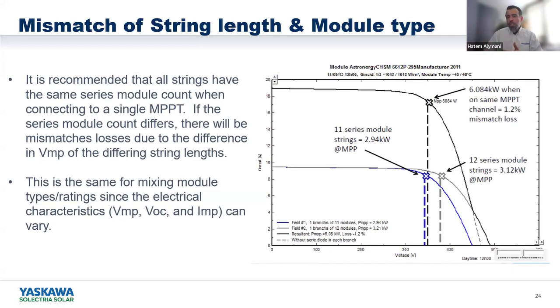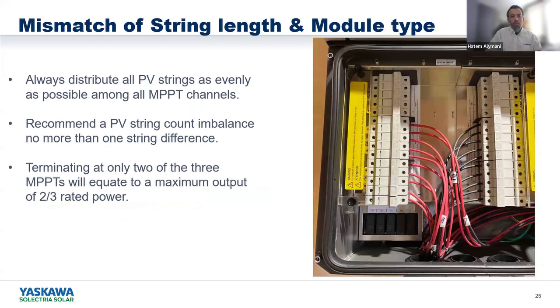Not only the string length and the same exact modules, but also the orientation of the modules on the MPPT: they all have to be facing the same azimuth. So that's one of the issues that we usually get asked about by our installers. The second issue is you have to always make sure to distribute all the PV strings evenly among the MBBTs.